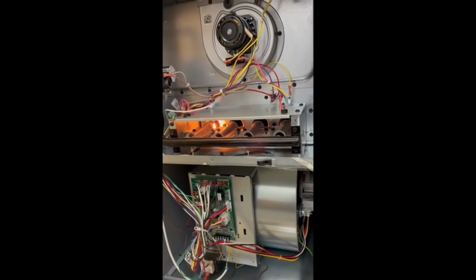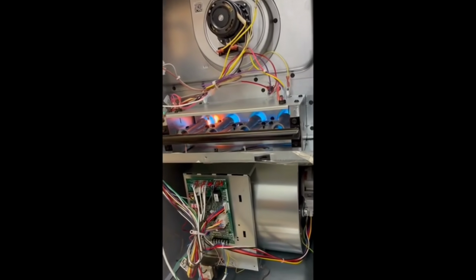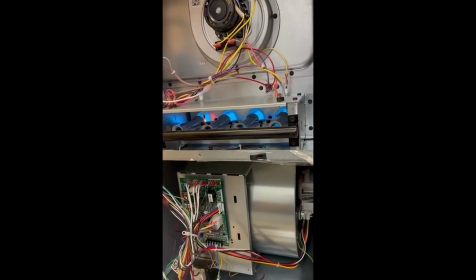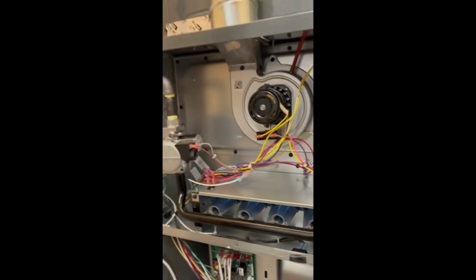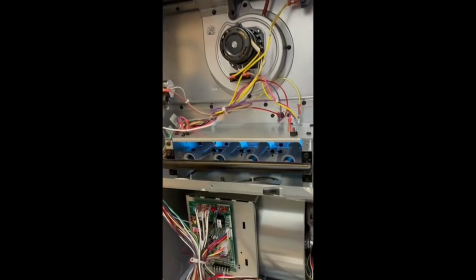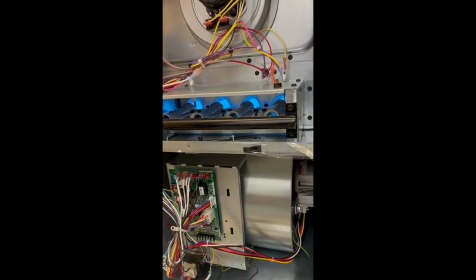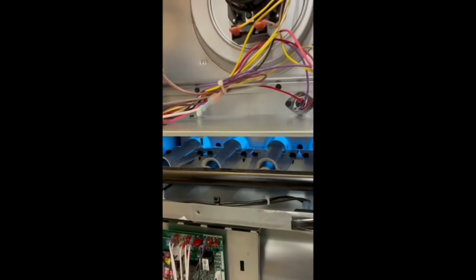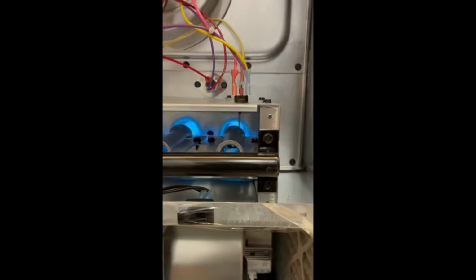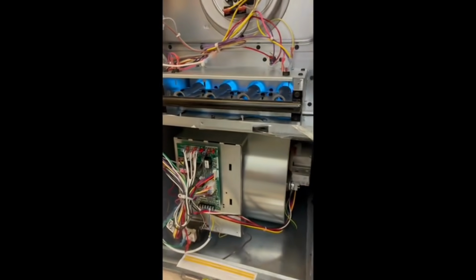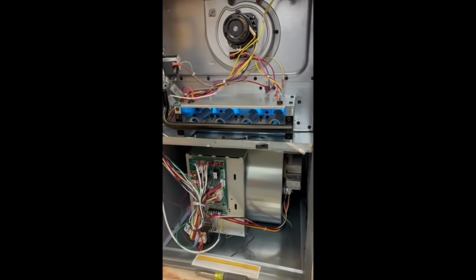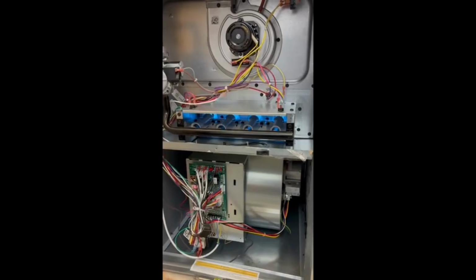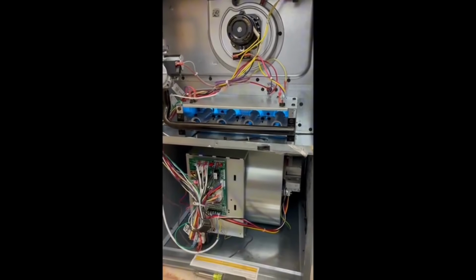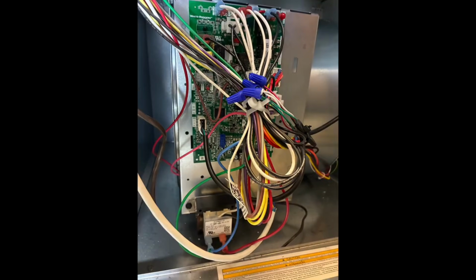Draft inducer fan running. Hot surface igniter is glowing red. Gas valve should open. Burners ignite. Looking good. Everything sounds good. Looks normal. You can also do a combustion analysis if you have that tool. This unit's good to go. I hope this video helps you. And remember to hook up your A2L refrigerant leak detection sensor.